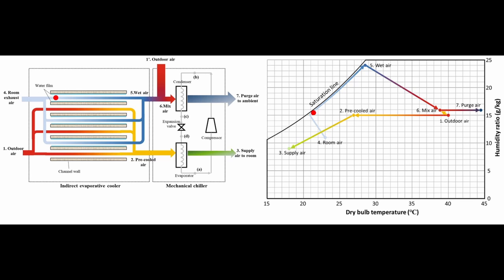After that, the dry bulb temperature and humidity ratio increase until the air has passed through the water film, where it now becomes wet air. The wet air will then be mixed with the outdoor air, where it turns to mixed air. As this happens, the wet air's dry bulb temperature increases while the humidity ratio decreases. The mixed air goes through the condenser where the dry bulb temperature increases and then is purged to the environment. And that is the process of the room exhaust air until it is purged to the environment.